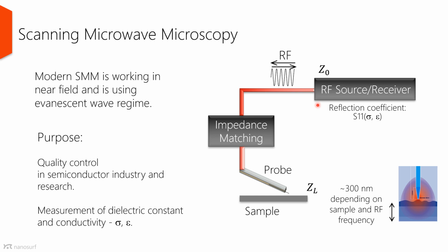Now, what kind of information can we get about the sample by doing this measurement? SMM is an electrical mode. The microwave properties of the sample depend on the dielectric constant of the material and its conductivity. And these two quantities are essential for the development of electronic devices, mostly semiconductor materials, where this method really shines, providing strong contrast between the different materials and the areas of different dopant densities. Another very useful feature of this method is that, unlike most scanning probe techniques, we get information from below the surface. The microwave penetrates inside the material for a distance called the skin depth, and therefore the information is collected from the volume below the surface, allowing for subsurface imaging.